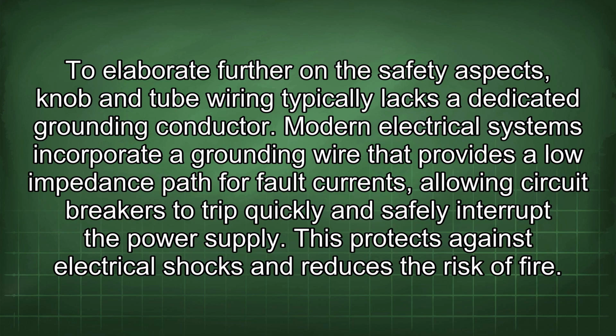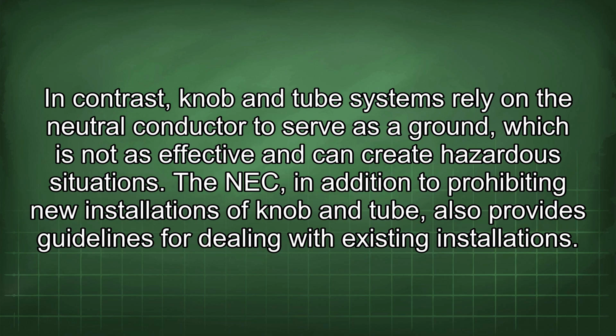To elaborate further on the safety aspects, knob and tube wiring typically lacks a dedicated grounding conductor. Modern electrical systems incorporate a grounding wire that provides a low impedance path for fault currents, allowing circuit breakers to trip quickly and safely interrupt the power supply. This protects against electrical shocks and reduces the risk of fire. In contrast, knob and tube systems rely on the neutral conductor to serve as a ground, which is not as effective and can create hazardous situations.